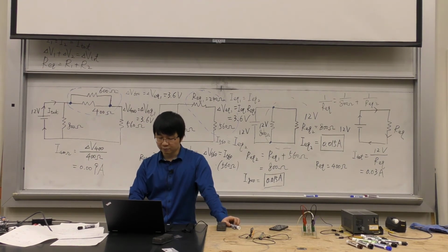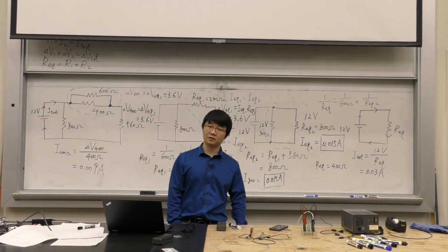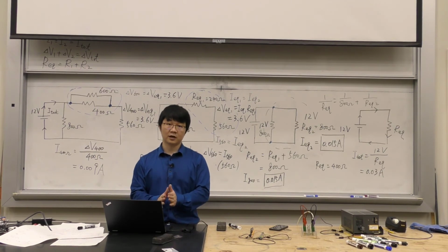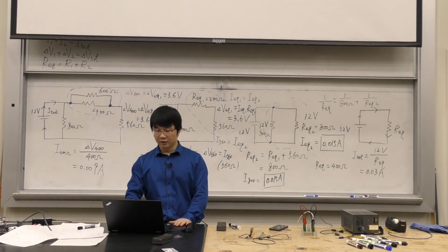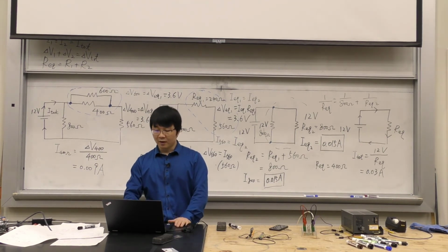Which is made of two different metals. And these two different metals are going to expand differently. They're going to expand at different rates when they're heated. So when the current gets too high, they get really hot, and so their expansion is different. So they're not going to become straight, they're not going to stay flat. The strip is going to bend one way depending on which one has a larger expansion, right?